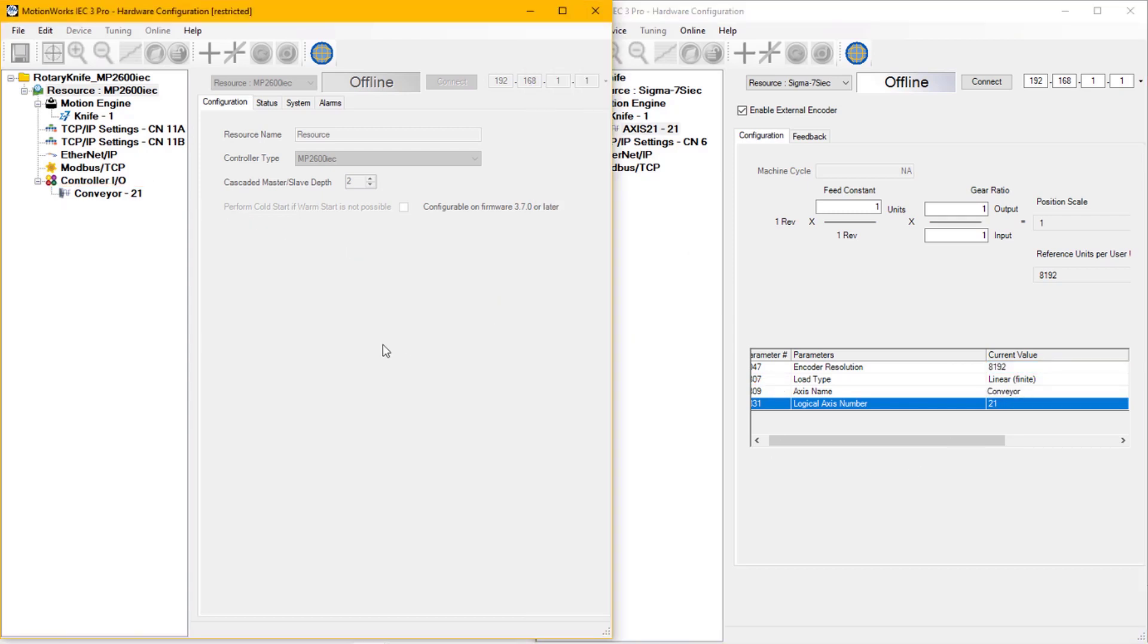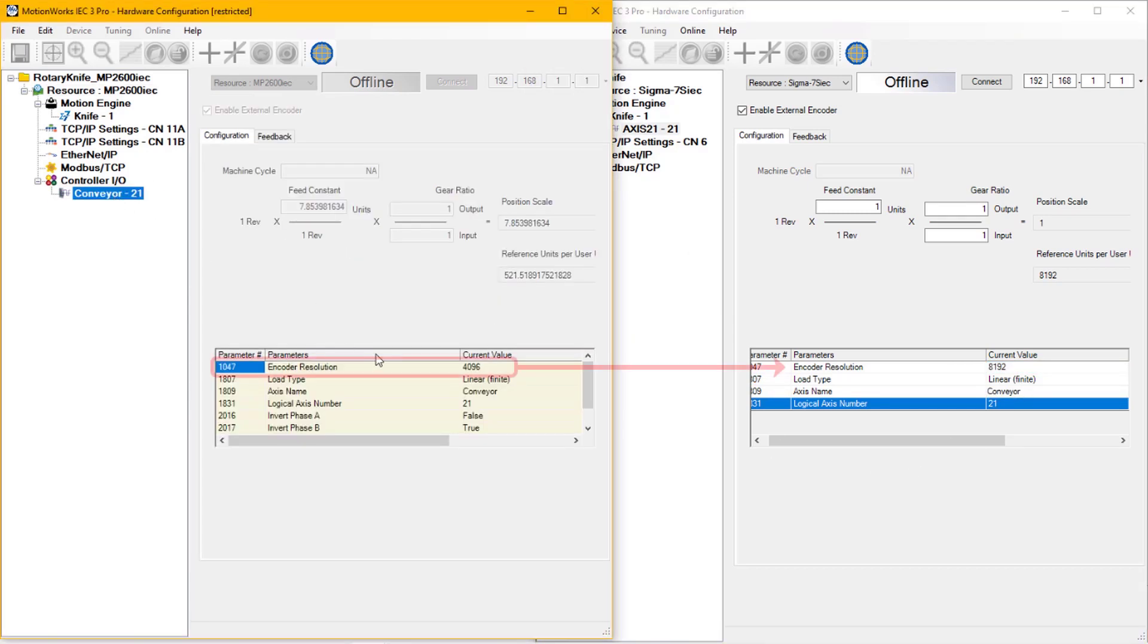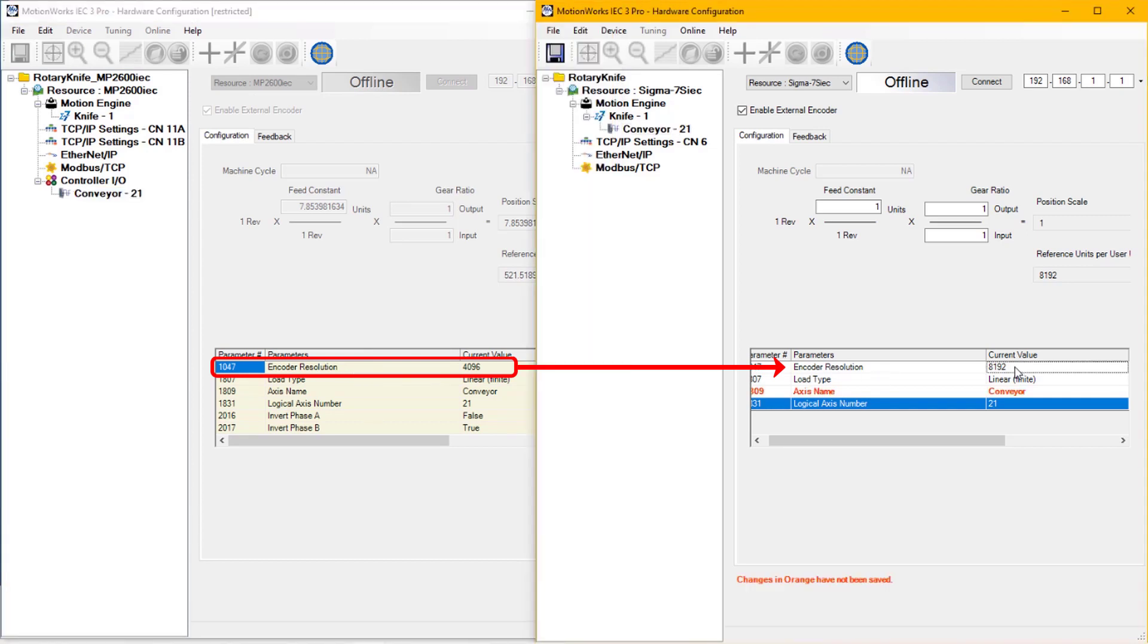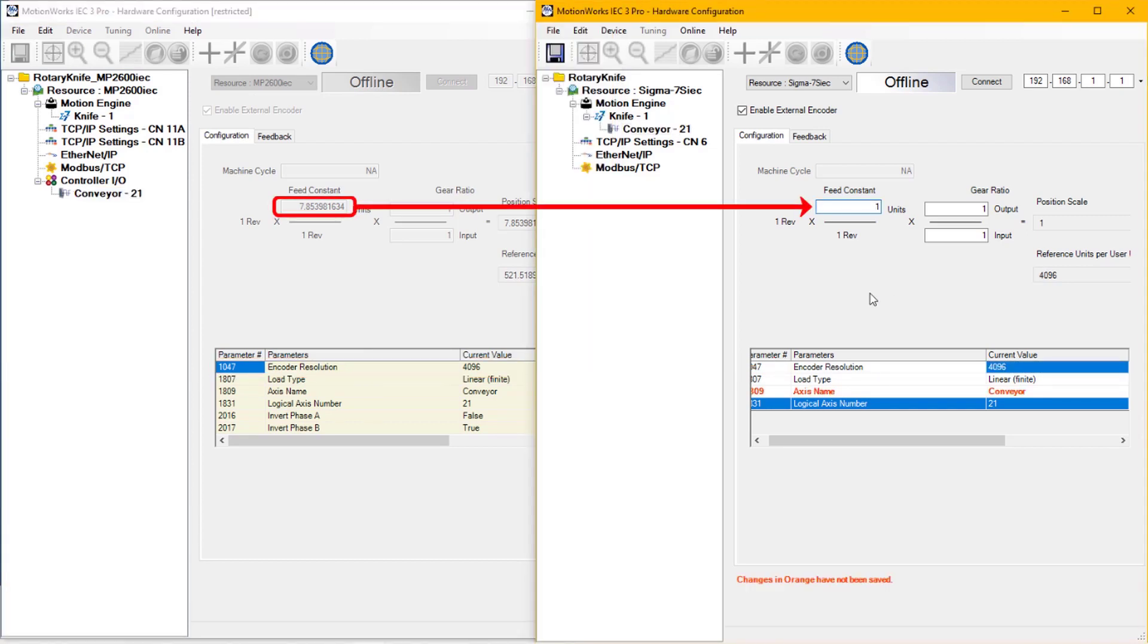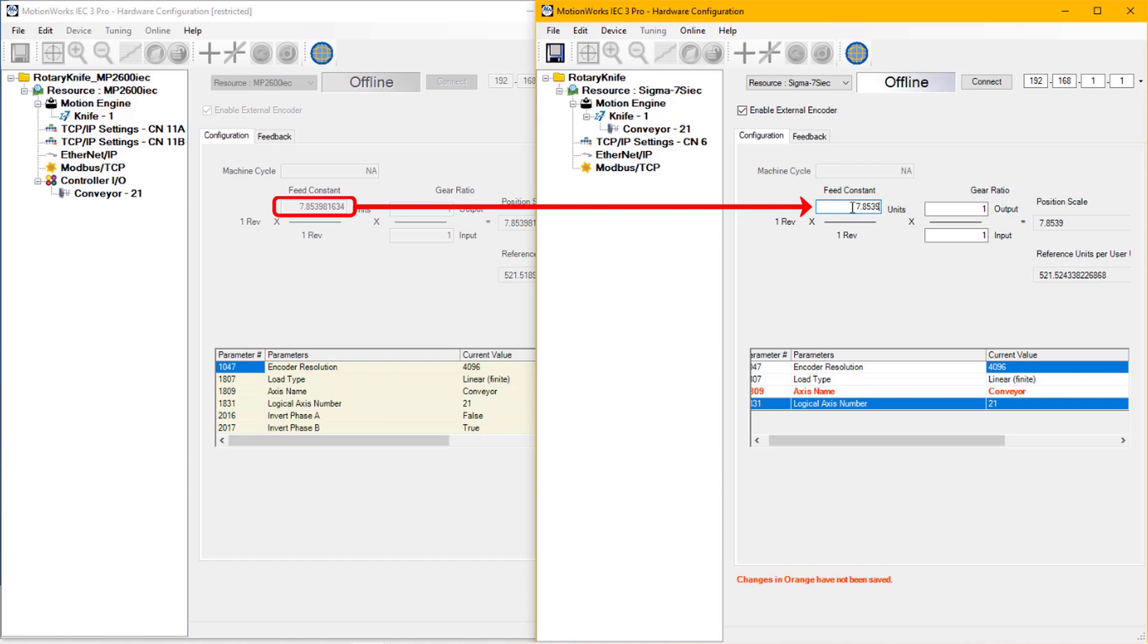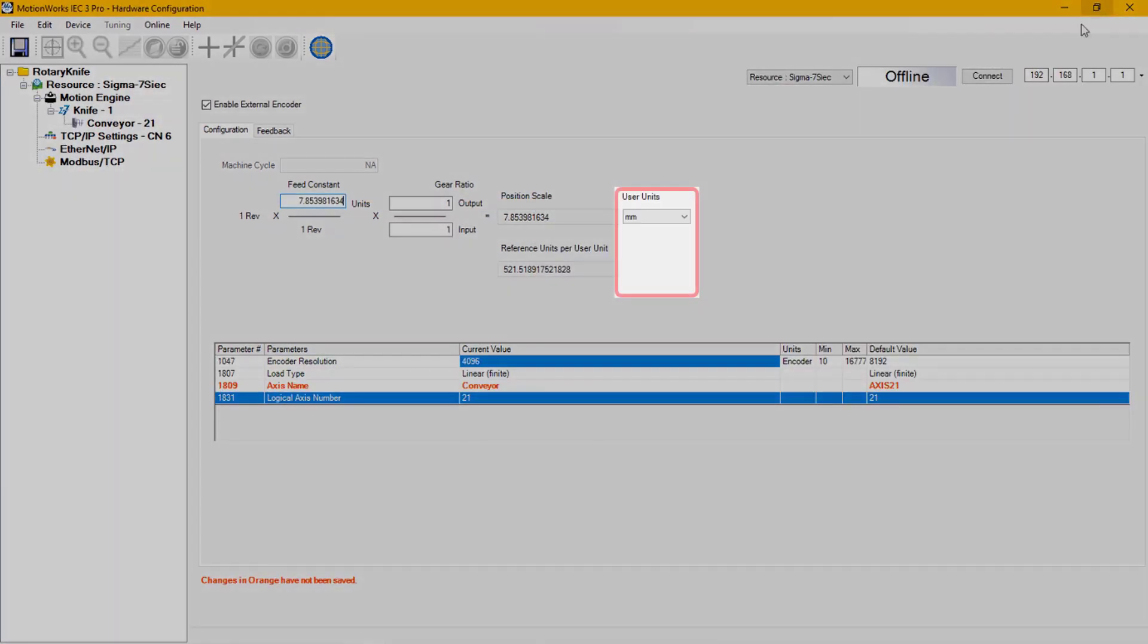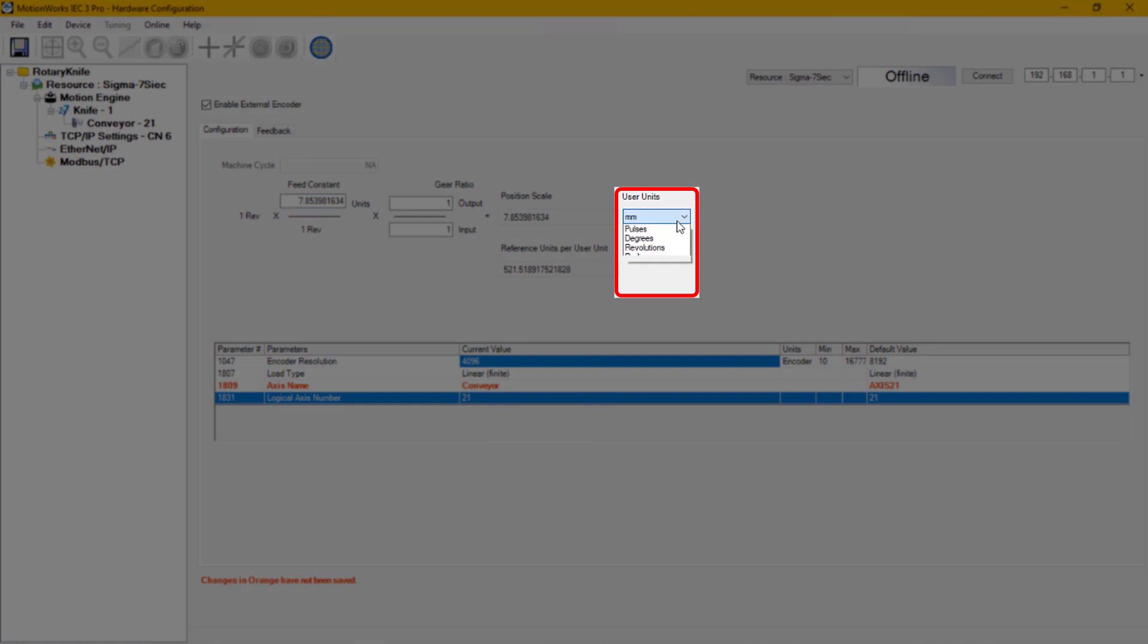Also looking at the MP2600 IEC project, we need to also set the encoder resolution to 4096. And I also need to set the feed constant, 7.853981634. And I have to set the user units to inches.